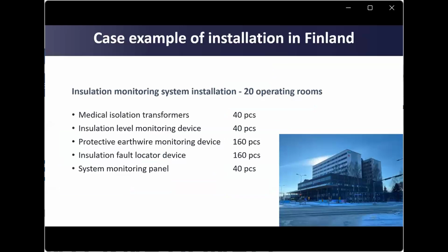Here is a case example of an installation in Finland. Insulation monitoring system installation for 20 operating rooms. What is required? Medical isolation transformers, 40 pieces; insulation level monitoring devices, 40 pieces; protective earth wire monitoring devices, 160 pieces; insulation fault locator devices, 160 pieces; system monitoring panels, 40 pieces.